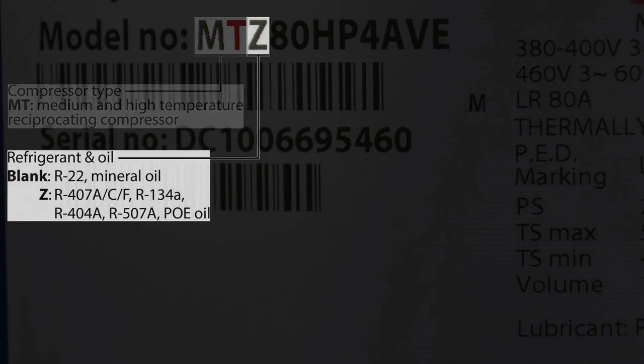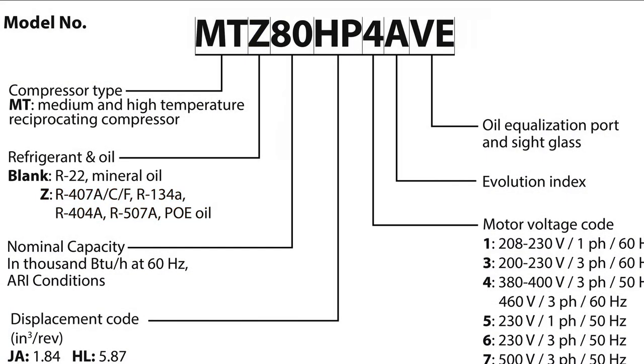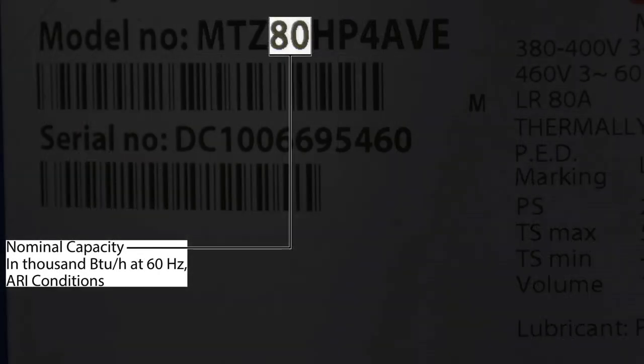The third digit signifies the oil and refrigerant. If the digit is skipped, the oil used is mineral oil with R22. If a Z is used, the oil used is POE oil with R407A, C, or F, R134A, R404A, and R507A. The next two to three digits of the model number signify the nominal capacity of the compressor in thousands of BTUs per hour.